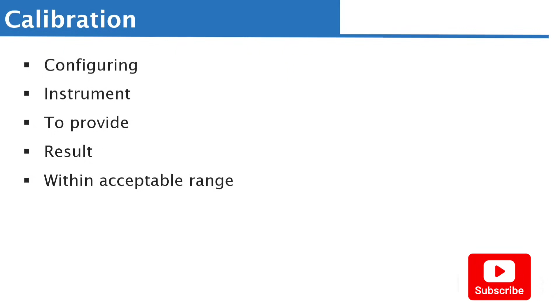Now, why do we do calibration? Remember, calibration is a form of quality management system. Obviously, from what I've explained to you, without effective calibration, without good calibration, you are likely not to get a reliable result. You are likely to get a wrong result. Therefore, calibration is a form of quality management system. We do calibration to maintain quality management system. We do calibration to ensure accuracy and reliable precision. We do calibration to ensure compliance, to make sure that the laboratory is within conformance, that the standard is maintained. So we do calibration as a form of instrument maintenance, to make sure that the instrument is functioning the way it's supposed to, to be able to give us a reliable result. We also do calibration to make sure that any form of deviation or any error will be corrected. Therefore, calibration helps to correct any deviations or errors. And again, we do calibration to maintain quality. I hope that makes sense.